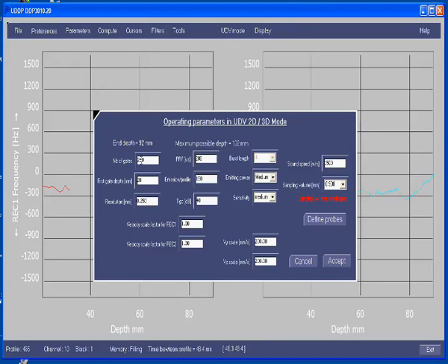The simulating software works with a fixed resolution. We will improve it to 0.250 mm. Changing the resolution changes the maximum measuring depth. In order to recover the original 90 mm, we will change the number of gates to 280. We will not change the other parameters and we will keep their value for the moment.